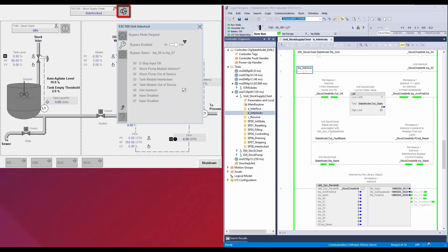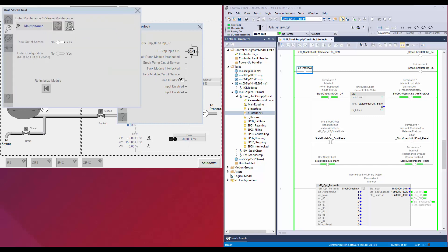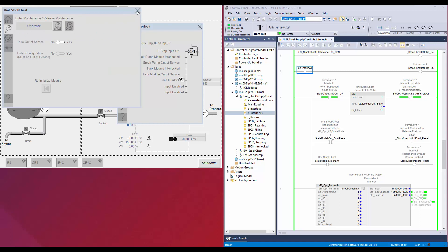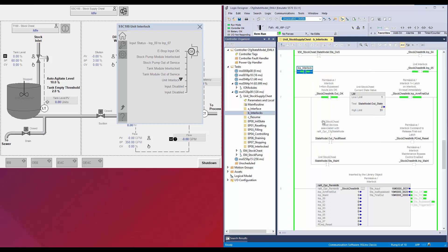I will bypass the input now. You can see the bypass indication and interlock OK status on the navigation button. I will open the home tab to show the input status. On the unit interlock input, there are two statuses being displayed: the input condition failed and the input is bypassed. I will release the maintenance control in the unit. You can see the unit is in idle state and ready for operation. When the interlock condition is OK, the faulted status will disappear.